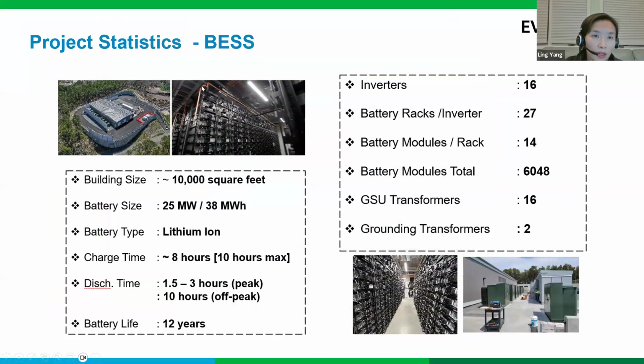This is the project statistics of the site. We have a building for this battery, and the building size is greater than 10,000 square foot. The battery size is 25 megawatts and 38 megawatt hours, and we use lithium ion batteries. Depending on the circuit loading, the solar charge time and the discharge time really depend on the circuit loads, and the life cycle of the battery is 12 years. We have in total 16 inverters and many battery modules and racks, and we also have 2 grounding banks for the site. So these are the statistics of the projects.